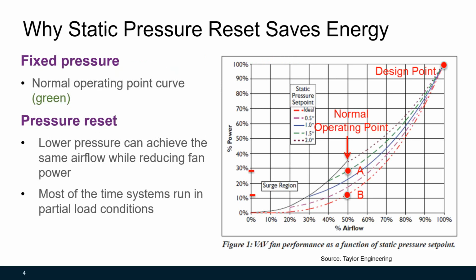First, let's take a look at why static pressure reset saves energy. Let's look at the chart, percentage of airflow versus percentage of fan power. In a typical VAV system design, the fans are designed based on the maximum cooling load, and the supply fan needs to run at a certain static pressure set point. In this example, the green curve represents the percentage of airflow versus percentage of fan power under 1.5 inches of static pressure. But the maximum design cooling load may only happen a couple of days a year.